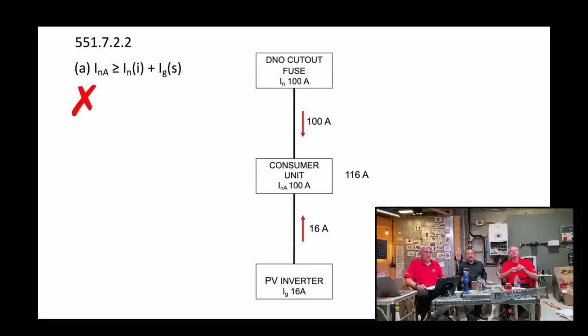Yes, and the equation at the top there, INA is the rated current of the assembly, IN is the rated current of the cutout fuse, and that needs to be greater than the cutout fuse and the generator basically. Nice and easy - you can clearly see there, pictorially, that's unacceptable.